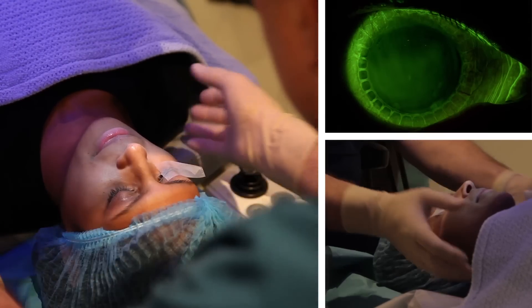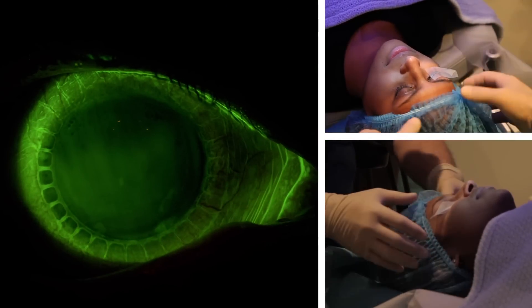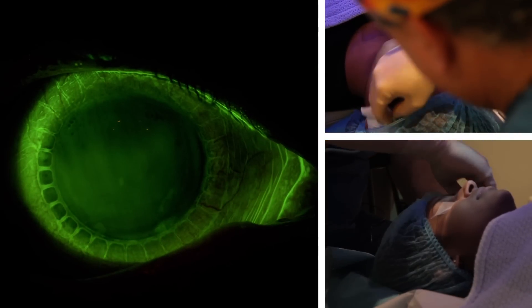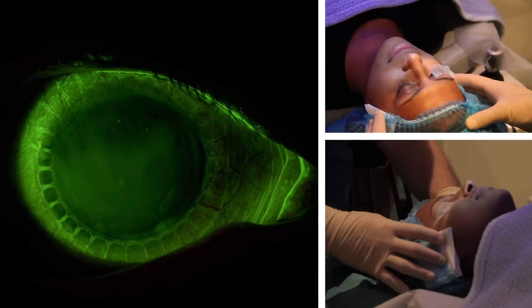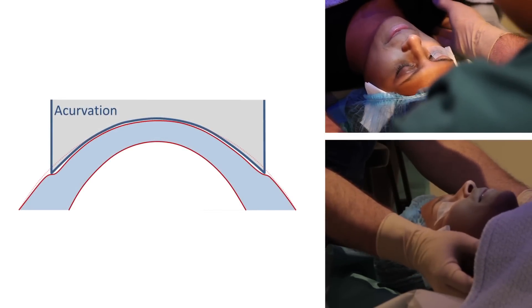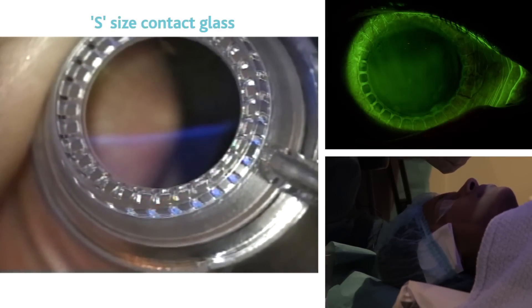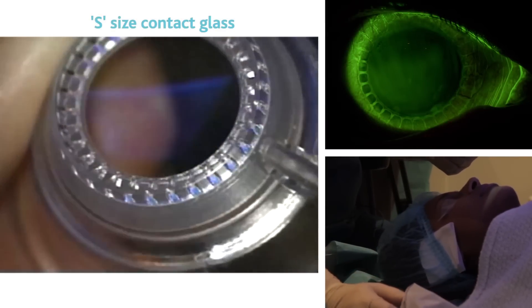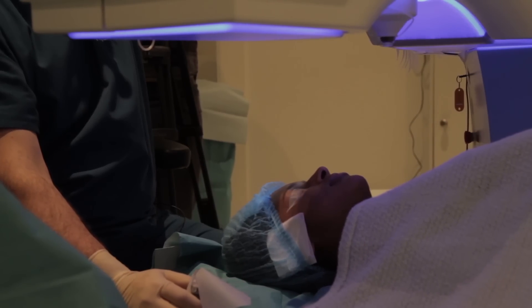Another important feature of the contact glass is that the suction ports are designed to lie on the peripheral cornea instead of the conjunctiva overlying the sclera, as in classical suction systems. The combination of curved application and corneal suction means that only very low suction is required to completely immobilize the cornea, minimizing corneal distortion and ensuring accurate 3D cutting within the corneal stroma.